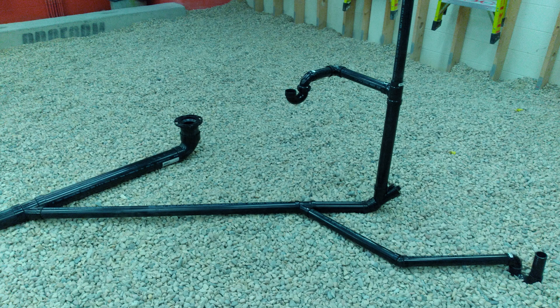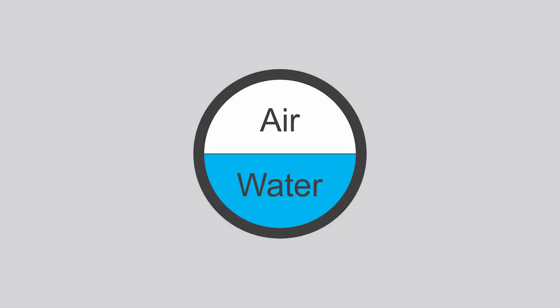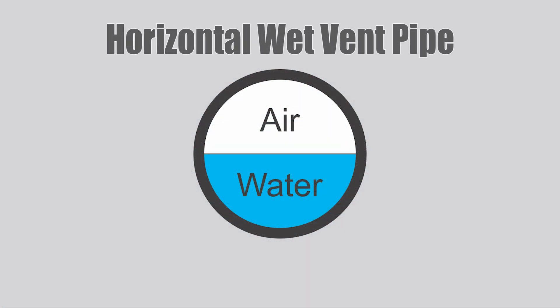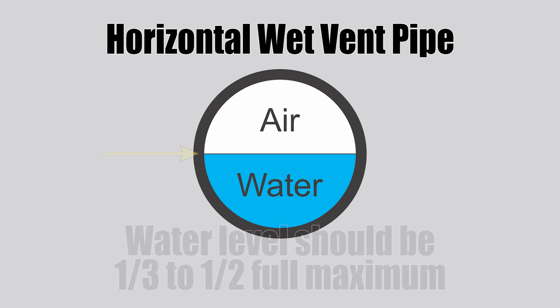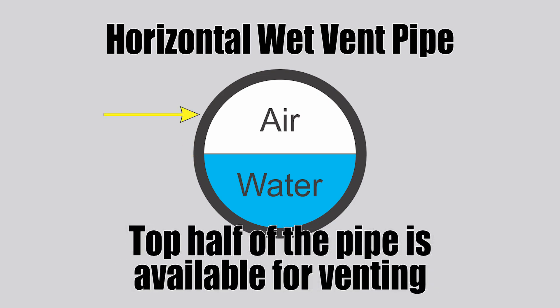We won't be sizing any wet vents in this video, but I'd like to show you the inside of a pipe that's being used in an adequately sized wet vent. You'll notice the water level should never come above the halfway point in the pipe, leaving the top half of the pipe available for actual venting.